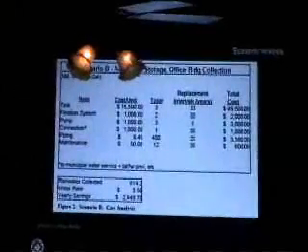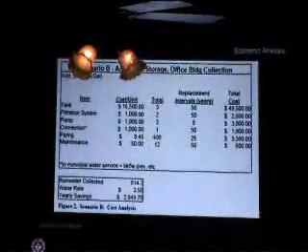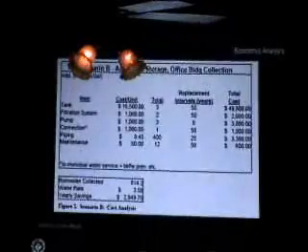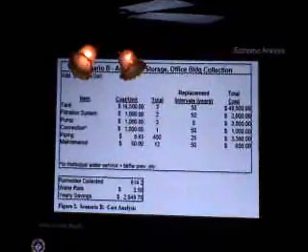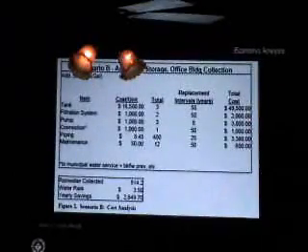So once we've taken all this information, added into the water demand models that you saw earlier, we outputted these panels for each scenario. What this is going to show you is just cost, replacement intervals, and total cost for the project itself. So scenario B, as I mentioned, we are adding 50,000 gallons of extra storage. So what you're looking at is the tank itself, being about $16,000 for the tank. Filtration systems, pumps, maintenance per year are all fairly negligible as far as cost goes. So we're looking at total cost for this project of close to $60,000.